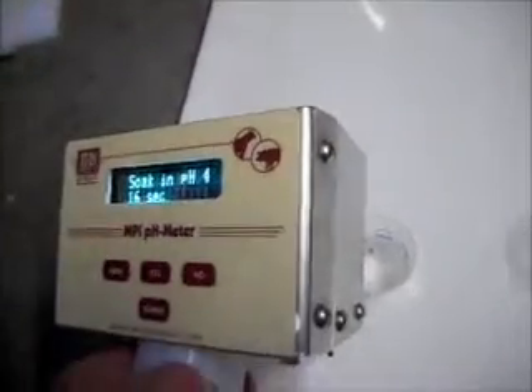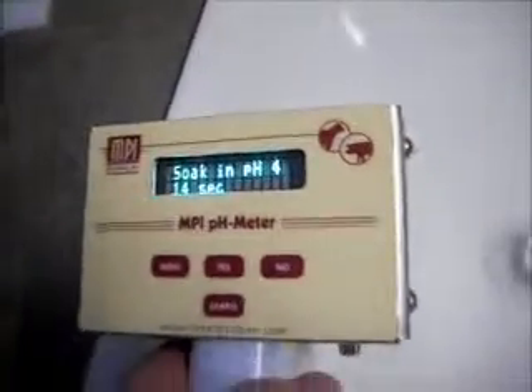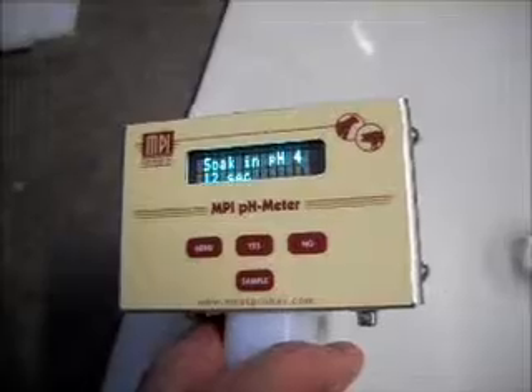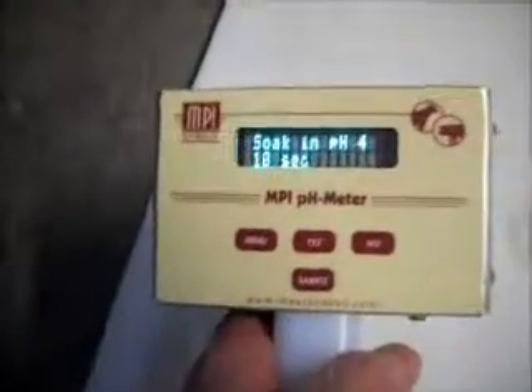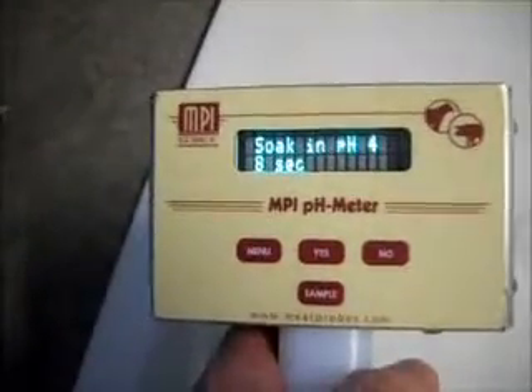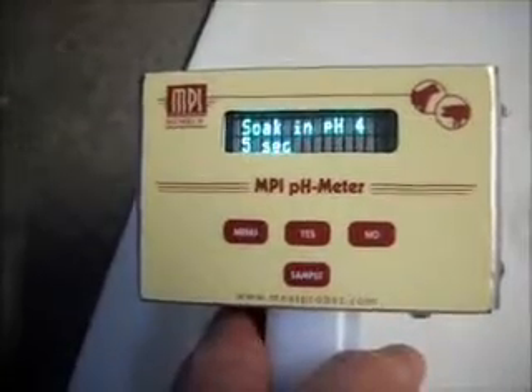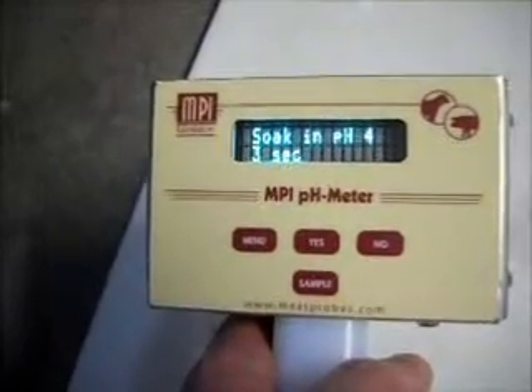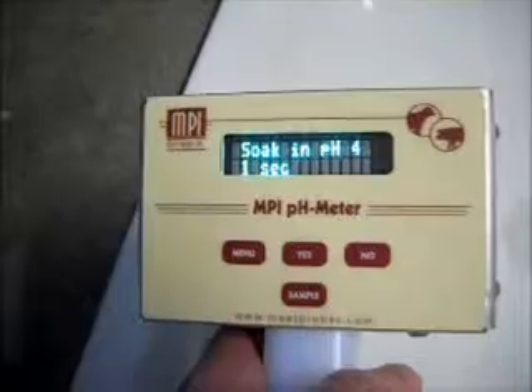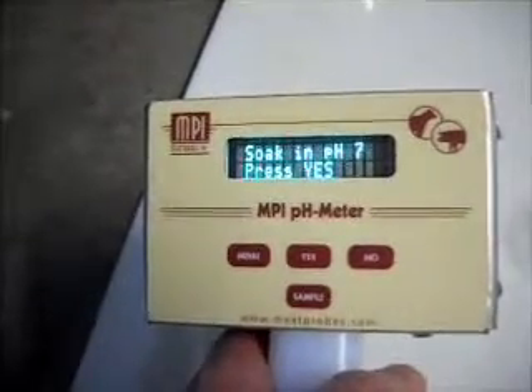So let's take a look here. We have the probe immersed in the buffer, and we're going to wait till it tells us to go to the next buffer. There are about 9 seconds left here, and when it's done, we need to wipe the tip off and then go to the next buffer. In this case, it's buffer 7. So we'll take it out, wipe it off, and then put it in the next buffer, which is buffer 7.